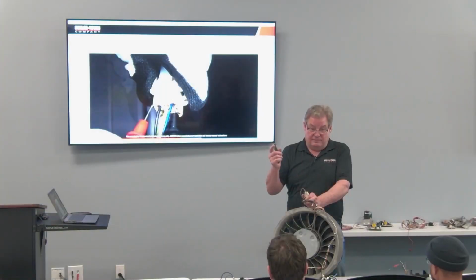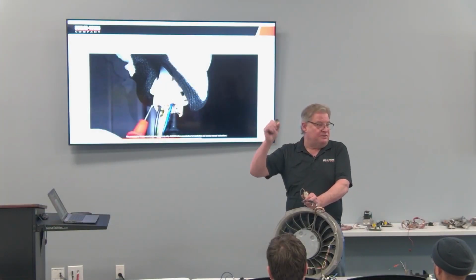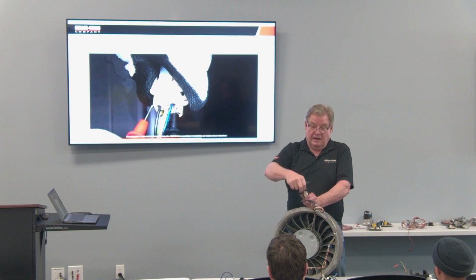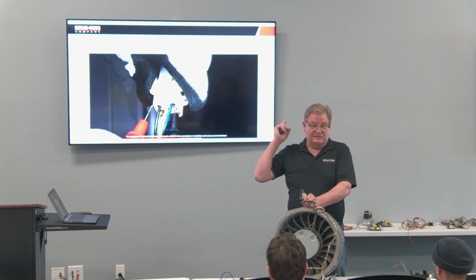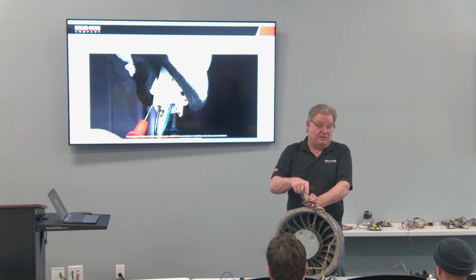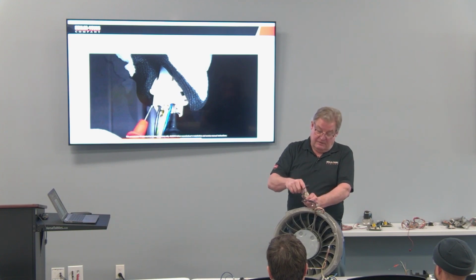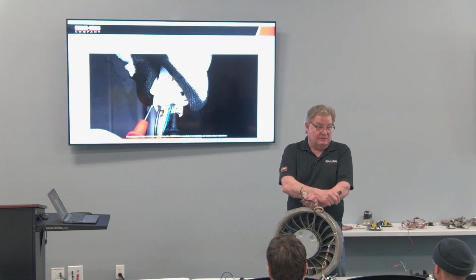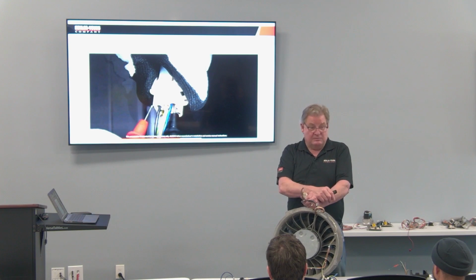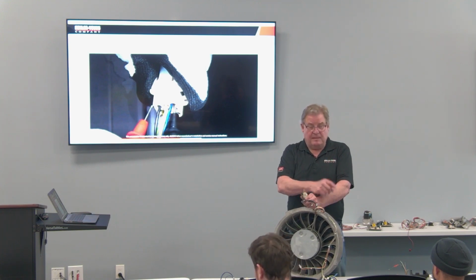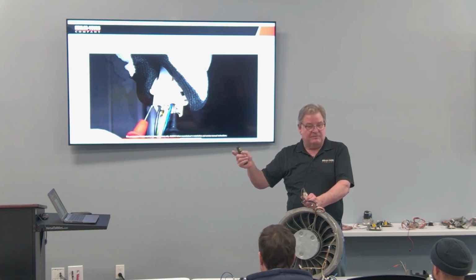So we're going to call for blower, right? I'm going to put a jumper R to G. And what should happen on the one we just set up? I should get 9 volts back down the gray wire from the board to tell the motor what speed to go. So if I go from white to gray and I have 9 volts when we're calling, the motor should be running. Again, if it's not, shut it off for 3 minutes before you fault it.